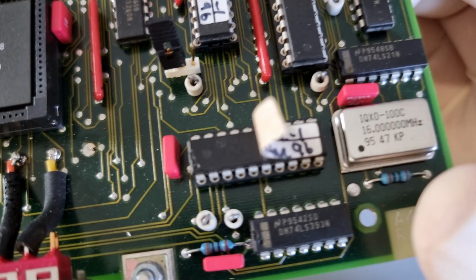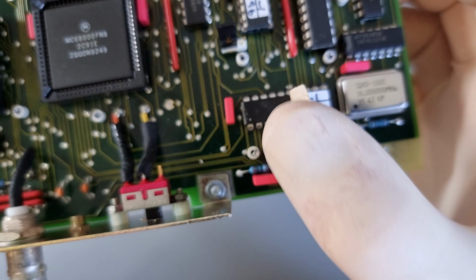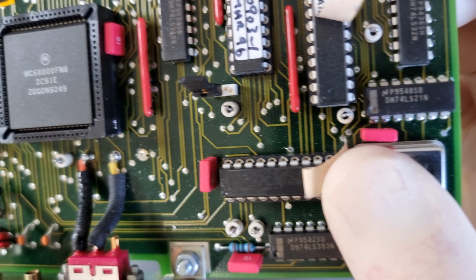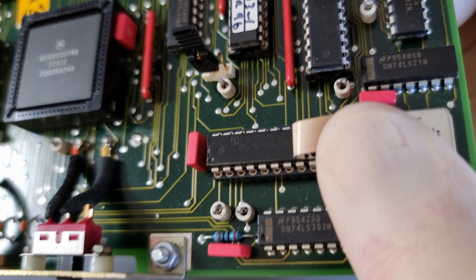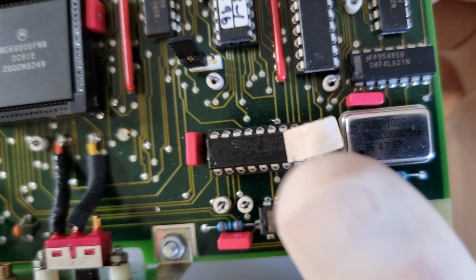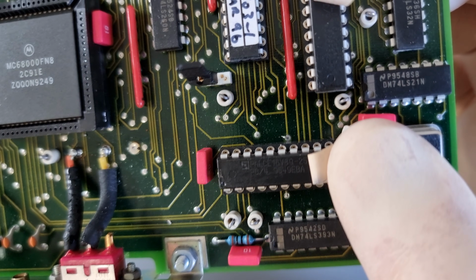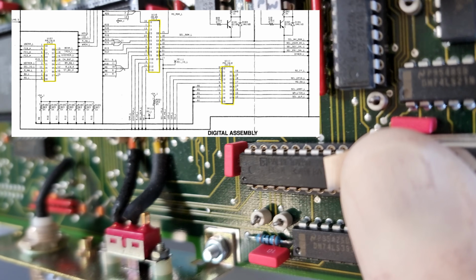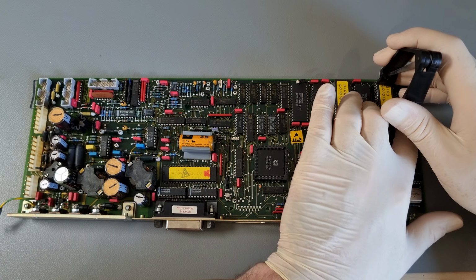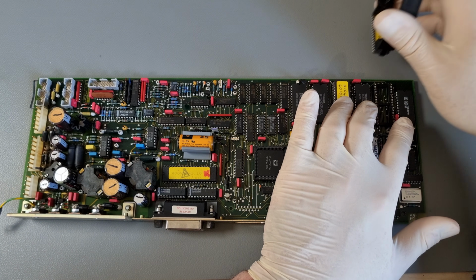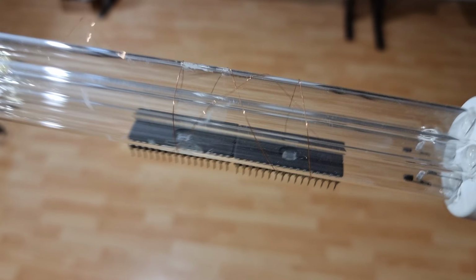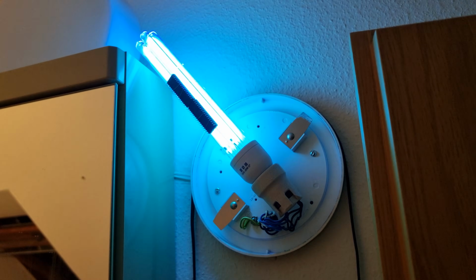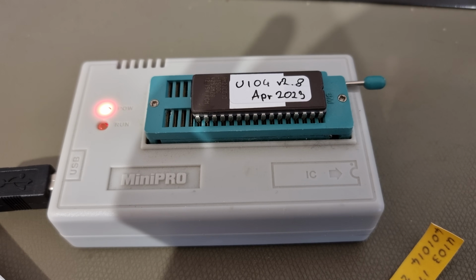The digital side of business is centered around a classic Motorola MC68000 microprocessor and a supporting CPLD that can be found, I think, in every single Datron of this era. These 3 labeled DIP parts are programmable array logic, almost FPGAs just without the field. They are helping with memory device selection and just overall device control features. I tried briefly to update the firmware on the UV EPROMs from 2.07 to 2.8, which is available on the XDevs servers. Unfortunately, this new firmware refused to work with my old programmable array logic, so I just ended up rewriting 2.07.